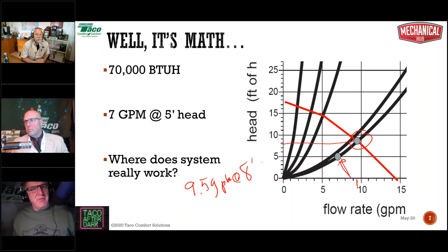Now, are we going to have any problems with the system working out there? Absolutely not. Can we deliver 70,000 BTUs with 9.5 gallons a minute instead of 7 all day long and twice on Sunday, and we're not even going to break a sweat? Does 8 feet of head cause any issues when I only need 5? None whatsoever. So from a standpoint of, is this system going to work? Yeah, I got no problems. Nobody's freezing to death and blaming me. I've done my job. Life is good. All right, that's the reality of the situation.